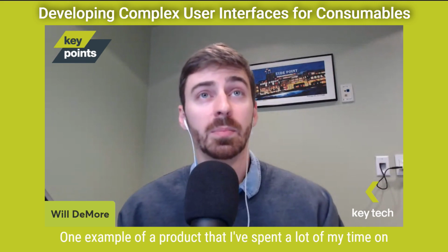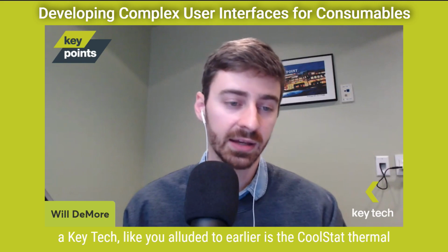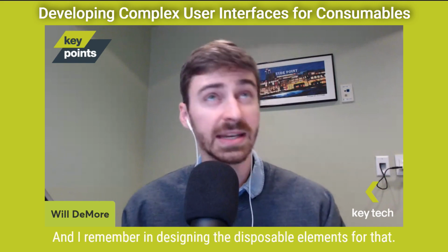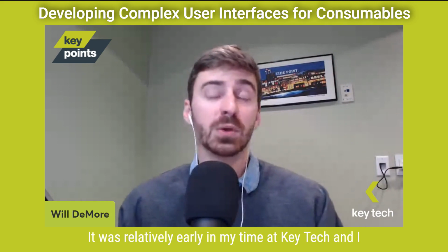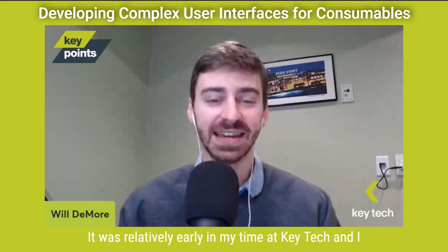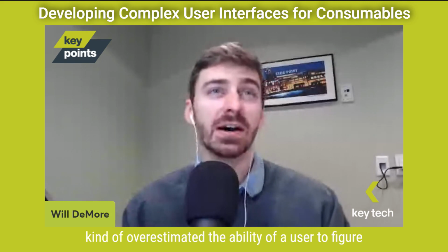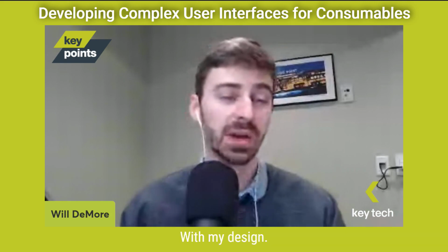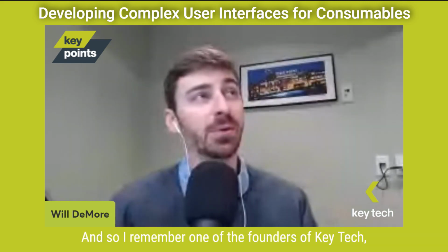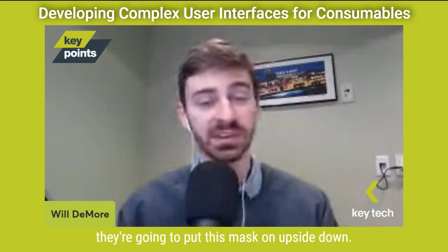One example of a product that I've spent a lot of my time on at Keytech, like you alluded to earlier, is the CoolStat thermal regulation device that we developed for Cooltech Medical. And I remember in designing the disposable elements for that, it was relatively early in my time at Keytech, and I overestimated the ability of a user to figure out right away exactly what I intended with my design. And so I remember one of the founders of Keytech, Brian Lipford, stressing to me that they're going to put this mask on upside down.